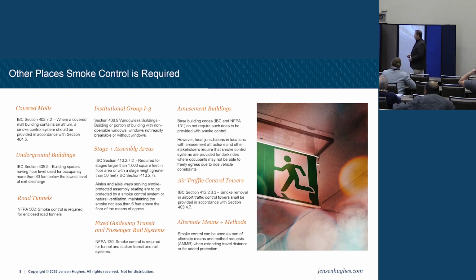Air traffic control towers. So air traffic control towers, I've spent a large percentage of my career running up and down the East Coast and out to the Midwest looking at air traffic control towers. The biggest challenge there is a lot of those towers were built with a single means of egress. So we want to make sure that means of egress is a safe means of egress no matter what the challenge. And some of those towers, 300 to 350 feet in the air. So it's a big challenge. And then alternate means and methods, right? Trying to accomplish something that isn't really allowed in the code, we could add smoke control as a trade-off.